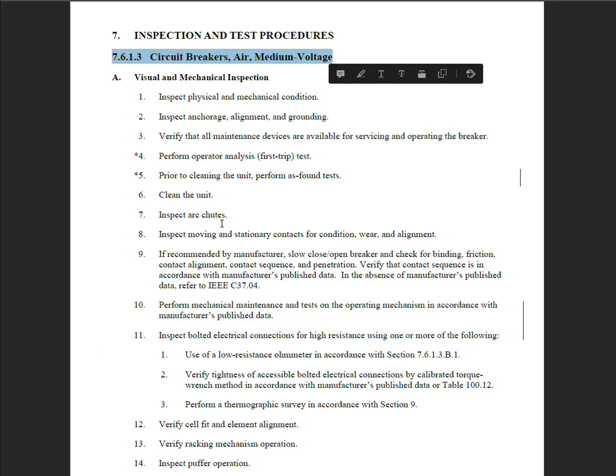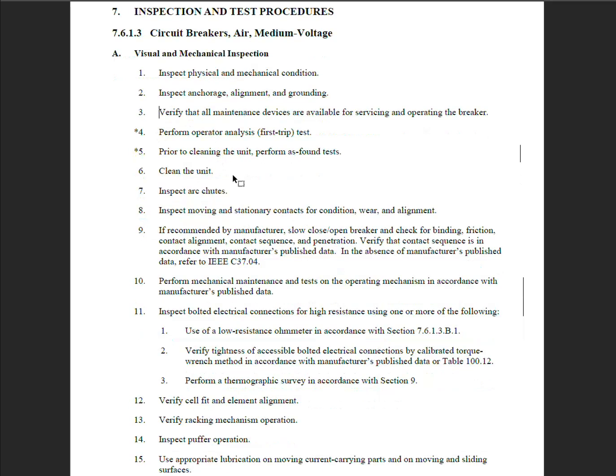So there's a lot of things to check here. This is an air circuit breaker, arc chutes, right? There's a lot of mechanical devices that you need to check on here. If you read this right here, perform slow close, if recommended by manufacturer. Perform slow close, check for binding friction, blah, blah, blah. Lots of stuff to check for. Okay, contact sequence, alignment, and it says penetration. Usually what that means is pressure. When you read the books, you'll see that.